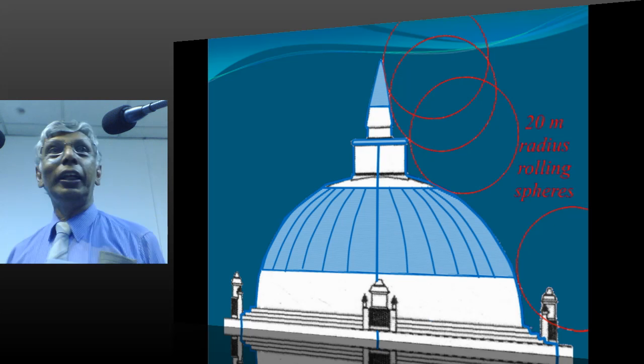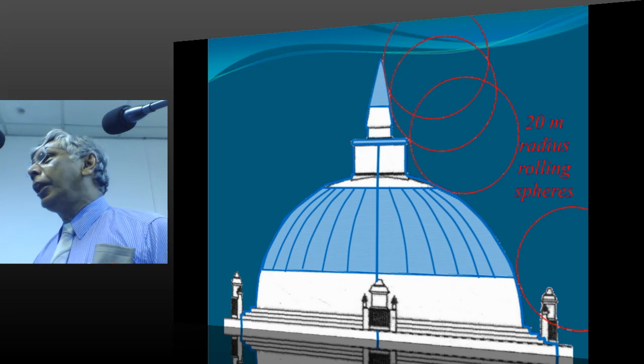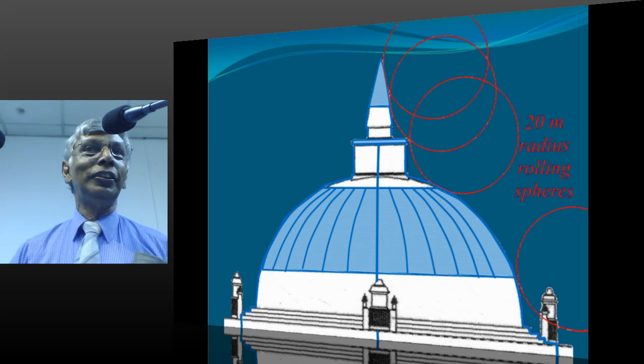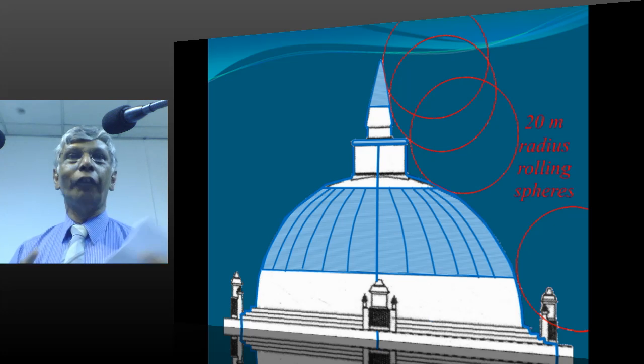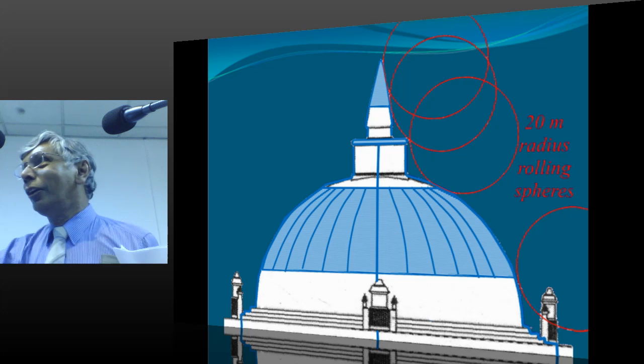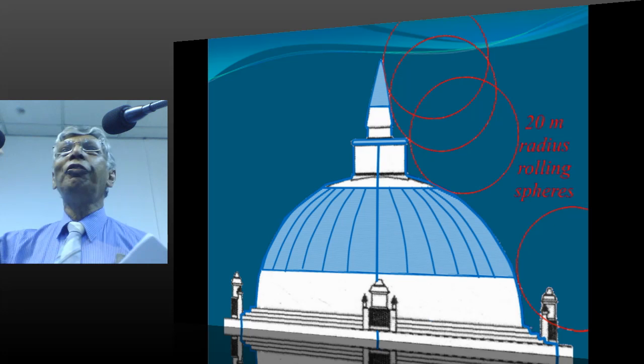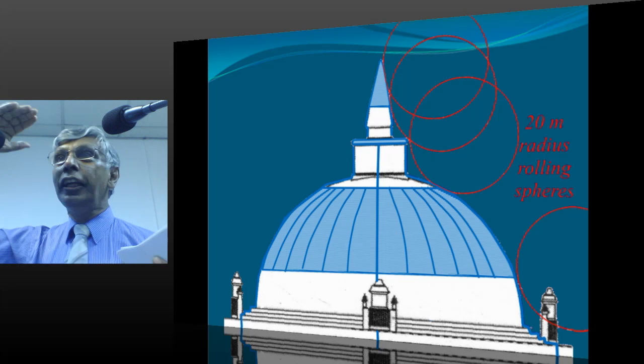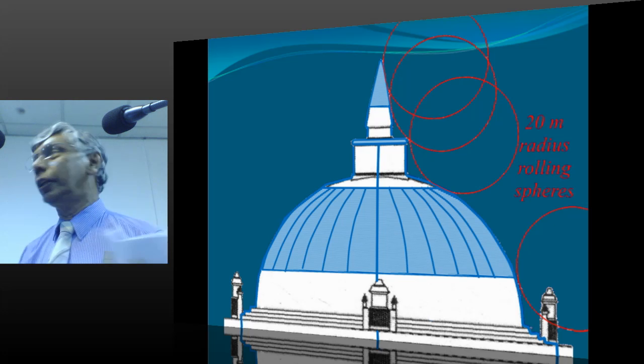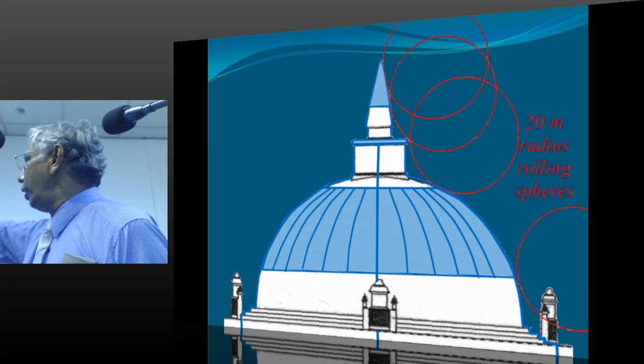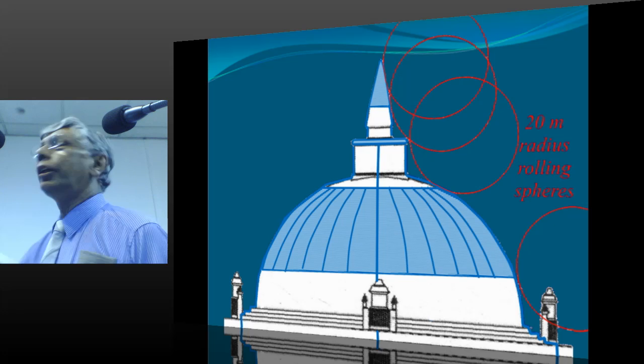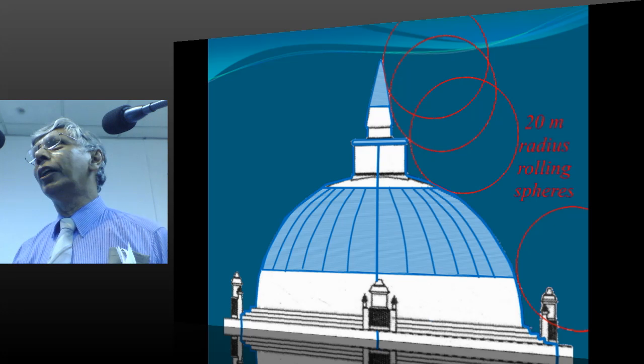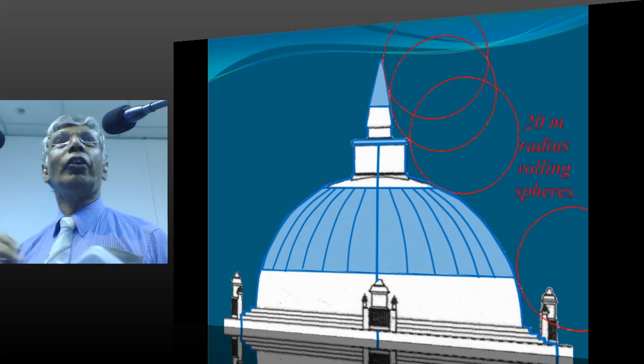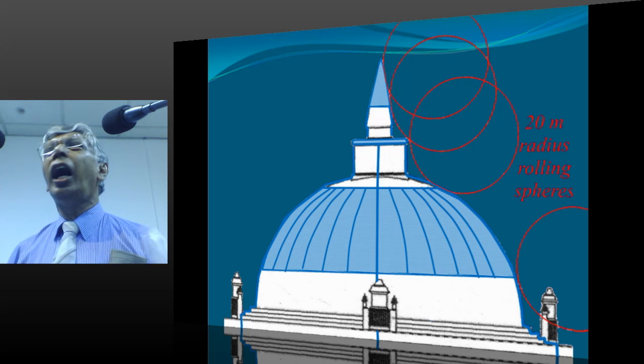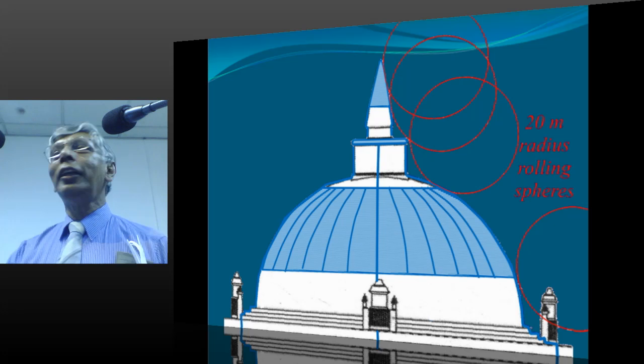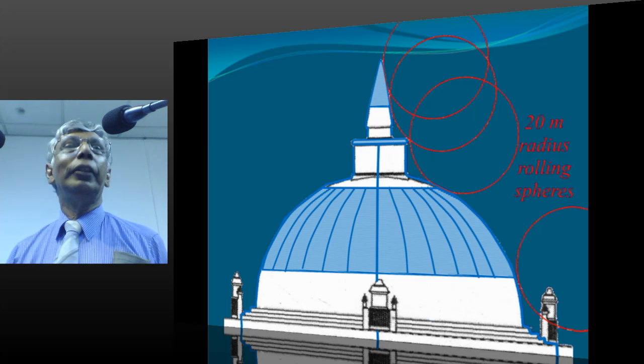But fortunately, the standards also say for buildings more than around 60 meters, you only protect the top 20% of the height, because lightning is not going to come down without striking the top portion. If the thing is more than about 120 meters, then anything more than that height needs protection. So even for side flashes, the middle part can be removed, only the top portion needs protection if you do need protection. If it is brick and a small portion of that kota gets damaged, I don't think it's such a serious problem. But if you invite lightning to come to the ground, that's going to be much more dangerous.